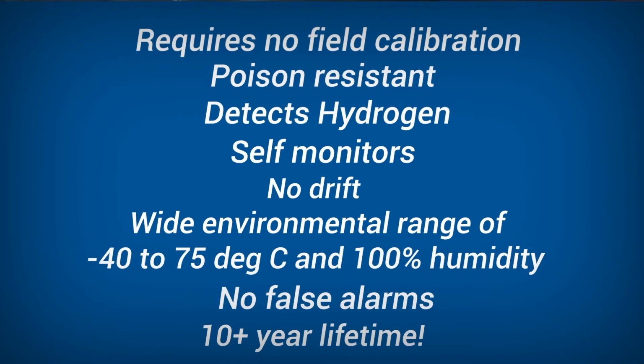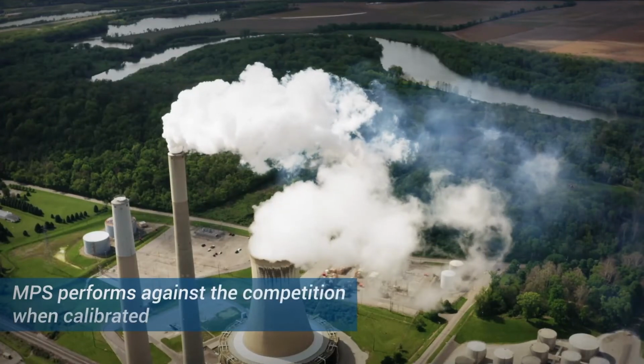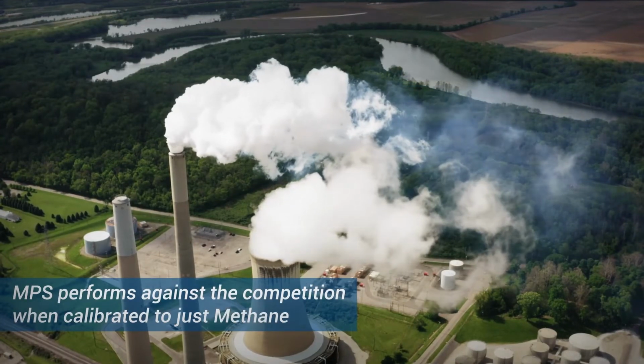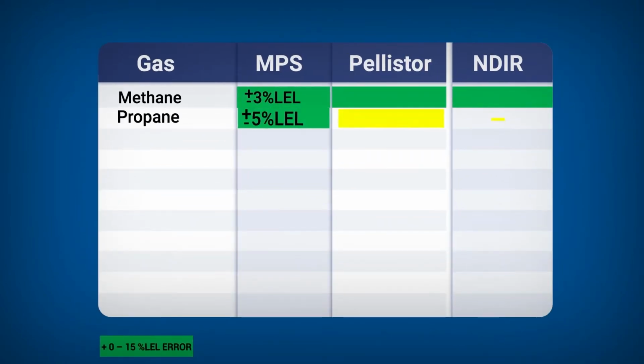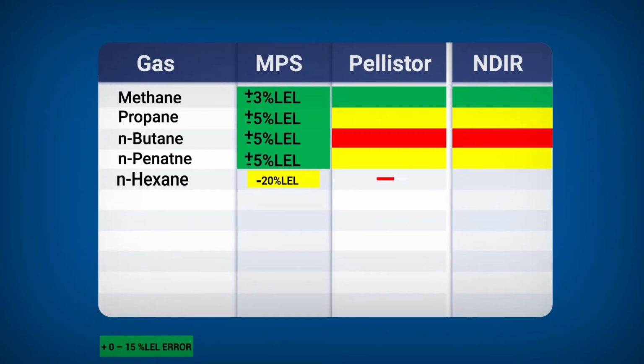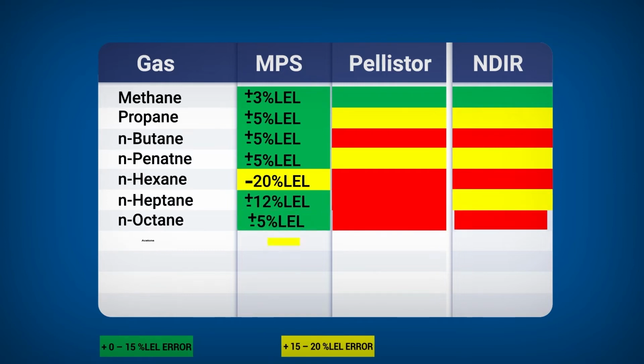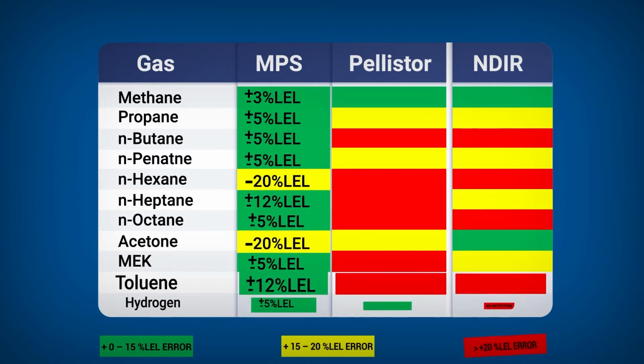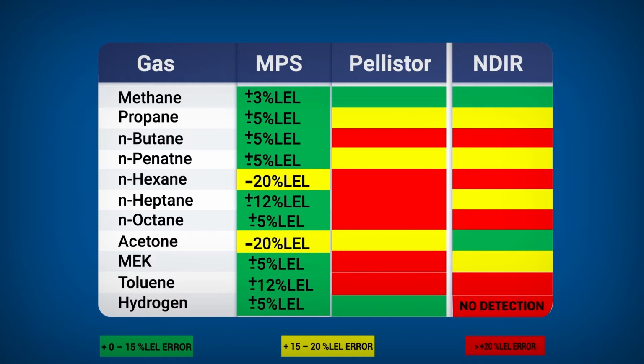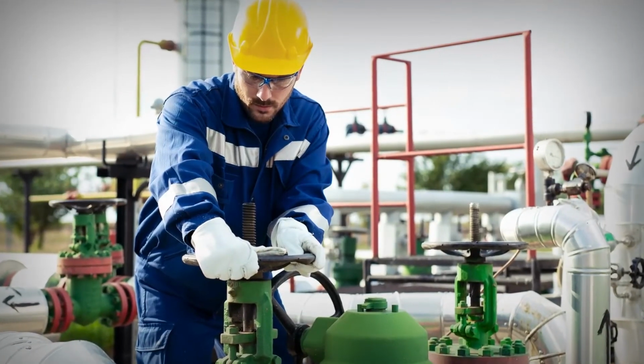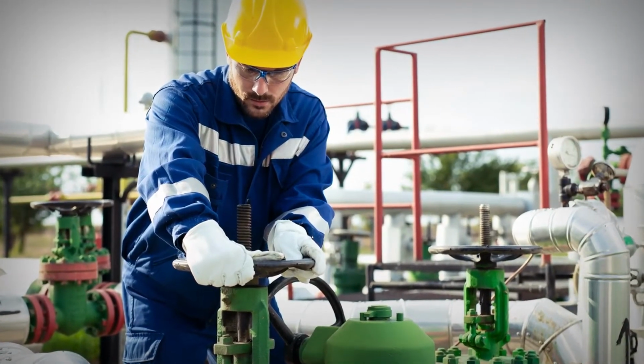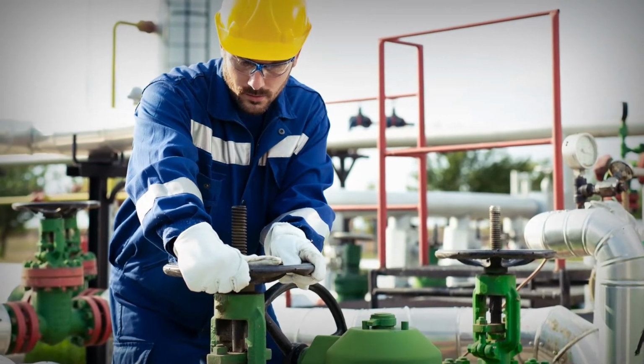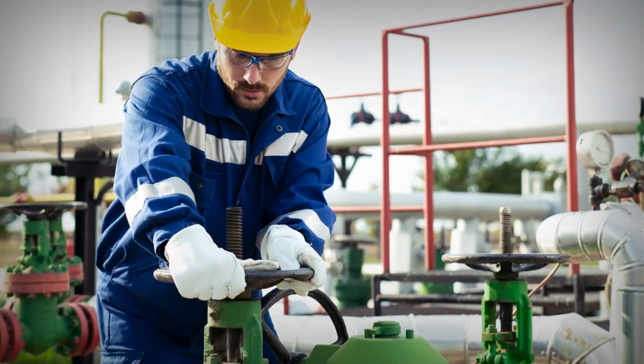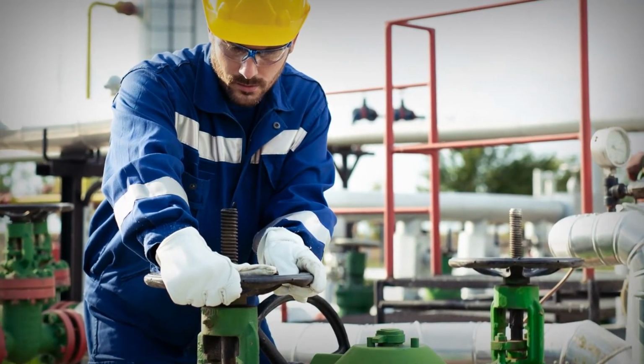Here we demonstrate how the MPS performs against the competition when calibrated to just methane. The MPS can accurately detect multiple combustible gases from one calibration, but traditional sensors are only accurate to the gas they have been calibrated to. When using traditional sensors, there is a real risk that hydrocarbons on your site will not be accurately detected, which puts your staff at risk.